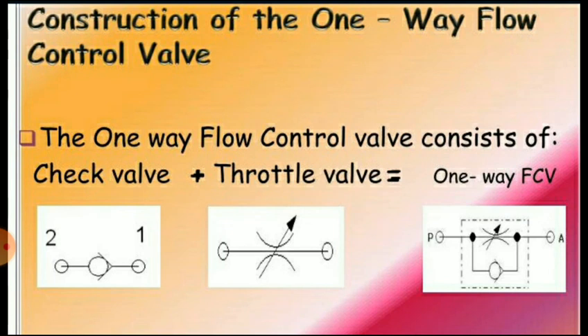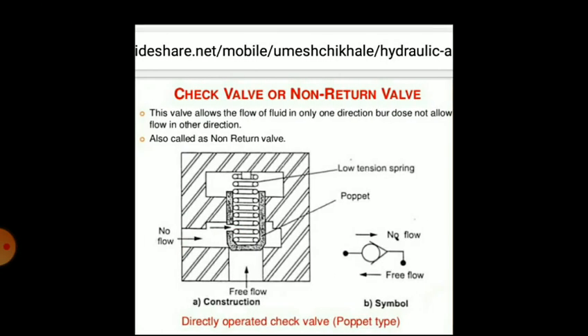Now we will see the construction of the one-way flow control valve. The one-way flow control valve consists of a check valve plus a throttle valve. The purpose of a check valve is to block the flow of fluid in a given direction but to permit unrestricted flow in the opposite direction. For this reason, they are also known as non-return valves. The flow blocking must be absolutely leak-free, and hence these valves are always of poppet-type construction.